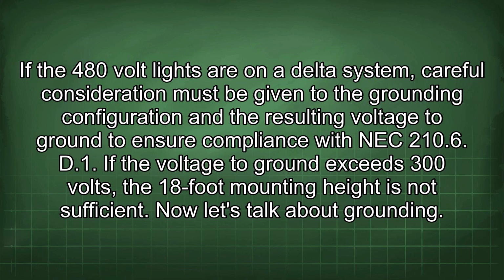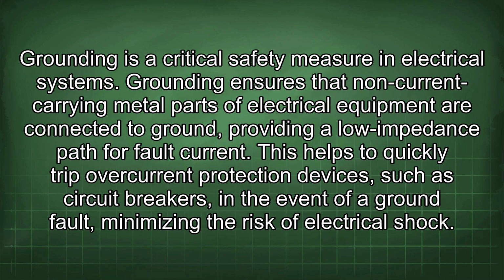Now let's talk about grounding. Grounding is a critical safety measure in electrical systems. Grounding ensures that non-current carrying metal parts of electrical equipment are connected to ground, providing a low impedance path for fault current. This helps to quickly trip overcurrent protection devices, such as circuit breakers, in the event of a ground fault, minimizing the risk of electrical shock.